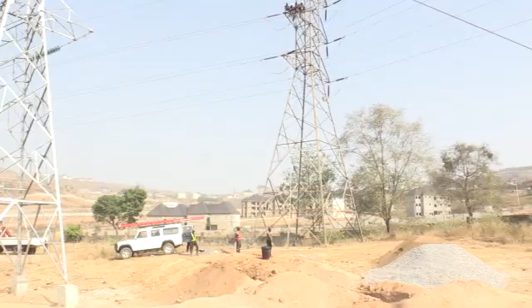This tower and line in question is the Katampe Central Area line. It feeds the central area where we have the 3 by 60 MVA transformers, supplying about 35% of power to FCT, that is the central business area. But being a proactive organization, we were able to divide the line, using another line from Katampe to feed the central area. The tower erection has since been completed and bulk power restored to the line supplying TCN Central Area Gas Insulated Substation.